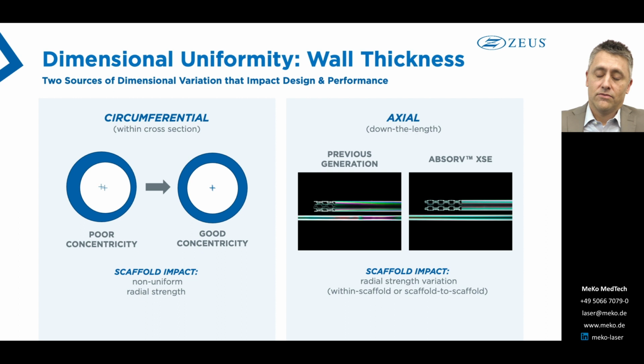So one of the main aspects of uniformity is dimensional uniformity, with most other aspects, such as mechanical property uniformity, really extending from there. So for tubing that's to be converted to a BRS, it's the wall thickness uniformity that's the most important, as there's a direct correlation with strut thickness in the BRS and the wall thickness of the tubing. Wall thickness variation, or we could call it non-uniformity, can rear its ugly head in two ways, either within cross-section or down the length, or axial, so circumferential or axial. We typically refer to within cross-section variation as concentricity.